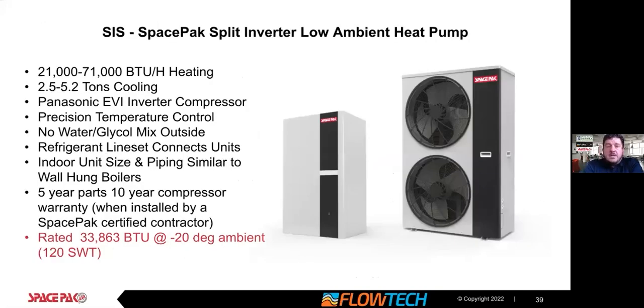So we wanted to focus on the low ambient, which is newer for us. I believe it's been in the market 4 to 5 months. This is very popular for us in our low ambient areas. So this takes the function of the monoblock and splits it up into an indoor unit and an outdoor unit. And in between, you have a maximum of 35 feet of line set. And so the low ambient gives us great performance. It also helps with the antifreeze protection, not needing as high a percentage of glycol. And the indoor unit kind of pipes up like a wall hung boiler.